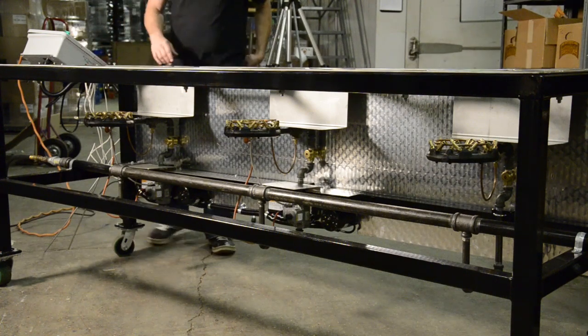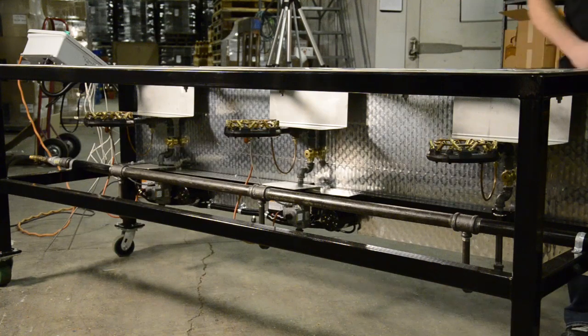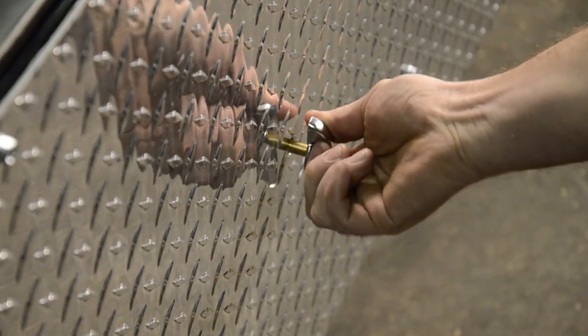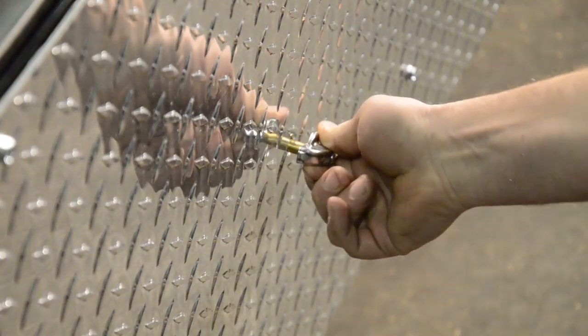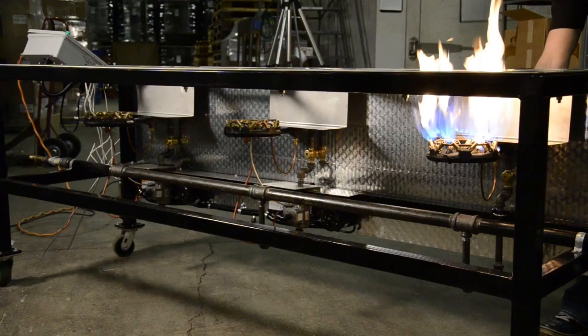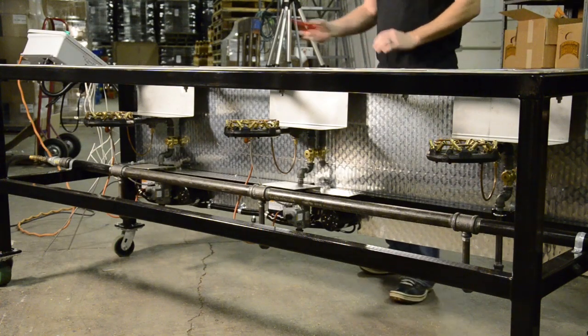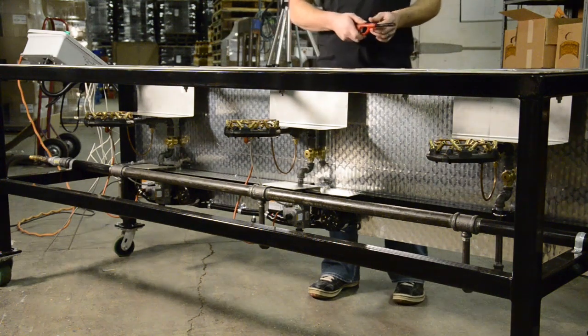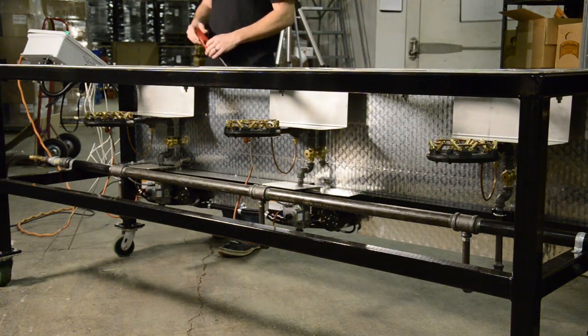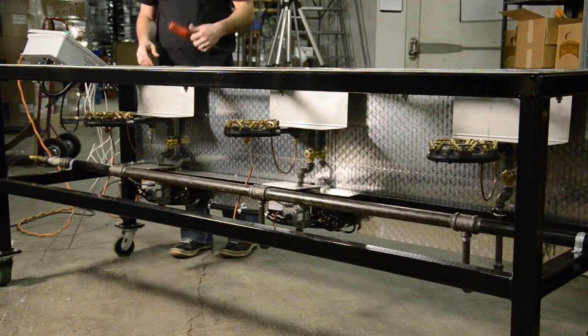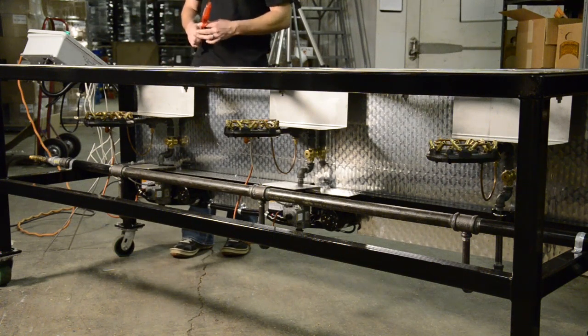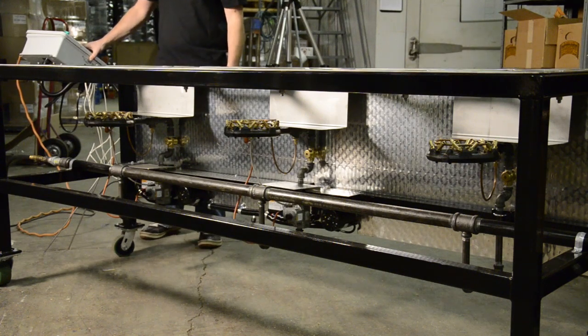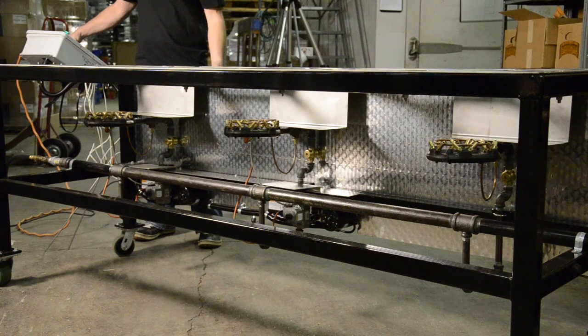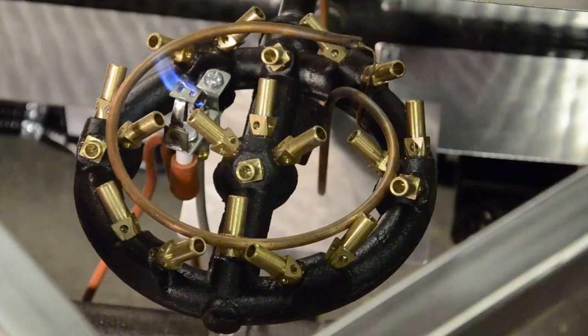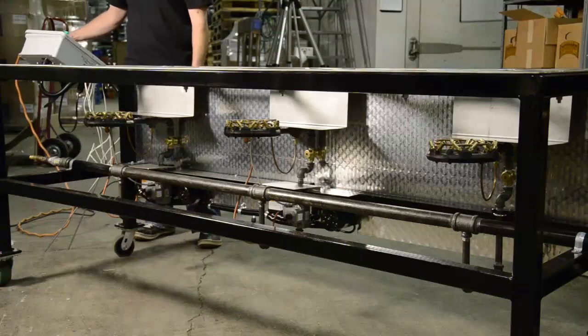At this point, what you'll do to start your cart is the end burner has a manual valve in the front. Open that until you smell just a hint of gas. Once that burner lights, you know your manifold has been purged of all air. After this, now it's time to light the main electronic valves. Keep in mind there will be some purge time, as the pilot tubes have to purge themselves from air. There's a 90-second trial time for ignition. So when you turn the heat switch on, there'll be a short delay. You'll hear a spark. Flame will be proven, and then main flame. Same with the other burner.